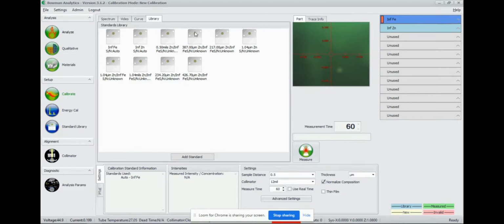The first thing that you're going to see over here is your standards library. Now this standards library has been slimmed down to only show the applicable standards that you've already got loaded into your standards library. So you're not going to see anything like cad on steel in here or gold, nickel, copper, because all we're doing is zinc on steel. Over here, we've got what standards we're actually using for our calibration.